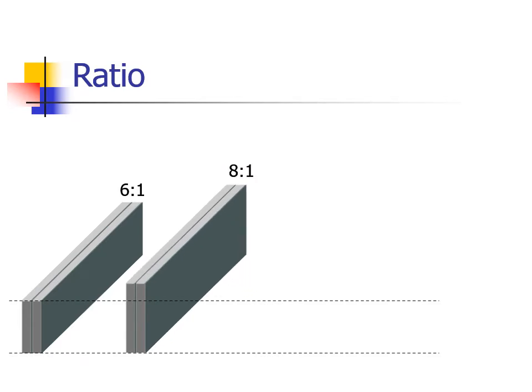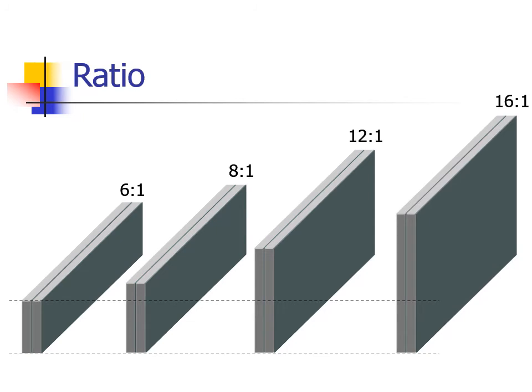Another common grid ratio is eight-to-one. Note that it is two units higher than the six-to-one grid. Twelve-to-one grids are commonly found in table buckies. Can you see this is twice as high as the six-to-one grid? A sixteen-to-one grid is probably the highest ratio you'll encounter in radiologic imaging. It is twice the height of the eight-to-one grid.